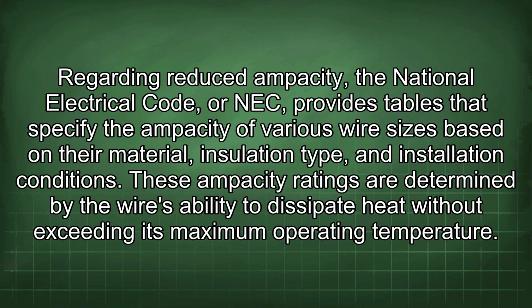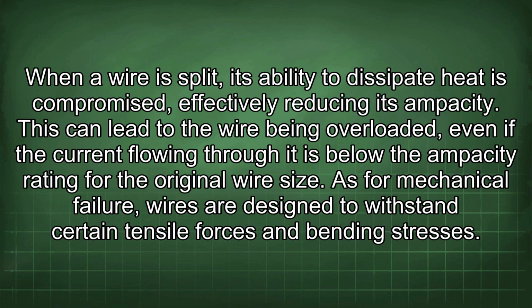Regarding reduced ampacity, the National Electrical Code, or NEC, provides tables that specify the ampacity of various wire sizes based on their material, insulation type, and installation conditions. These ampacity ratings are determined by the wire's ability to dissipate heat without exceeding its maximum operating temperature. When a wire is split, its ability to dissipate heat is compromised, effectively reducing its ampacity. This can lead to the wire being overloaded, even if the current flowing through it is below the ampacity rating for the original wire size.